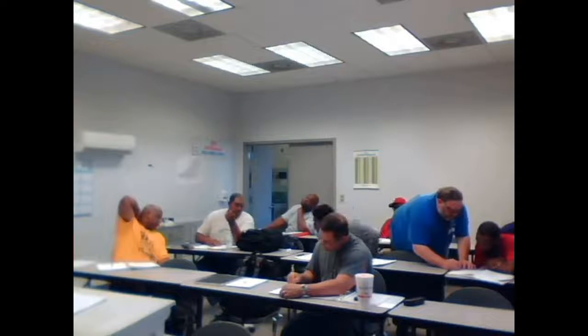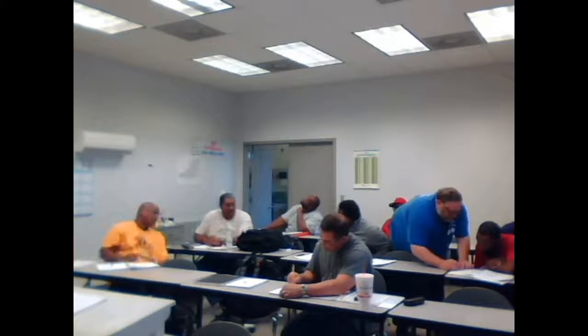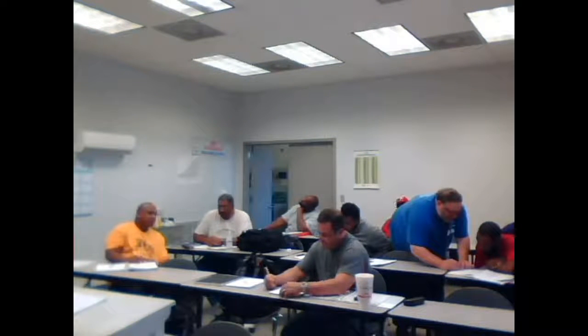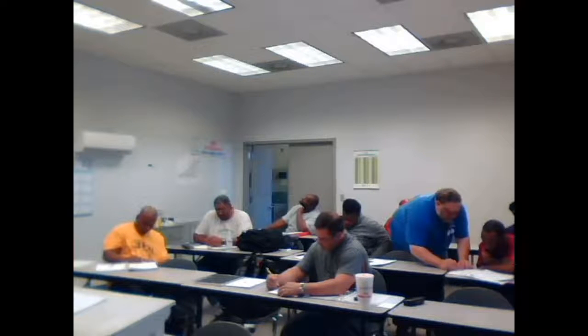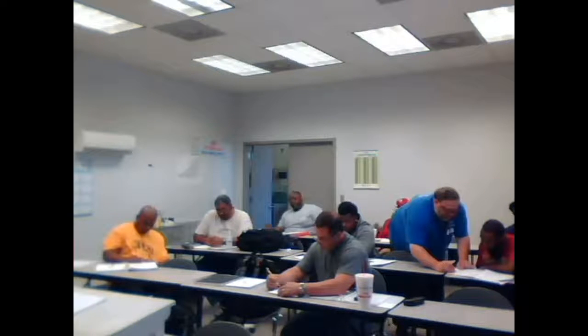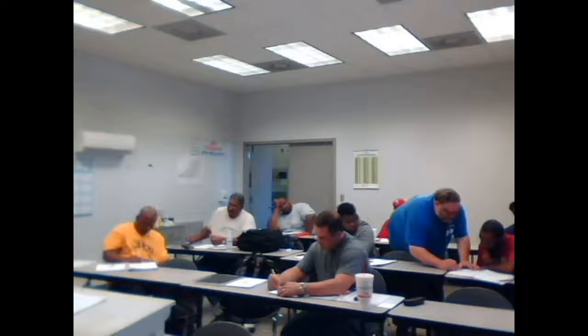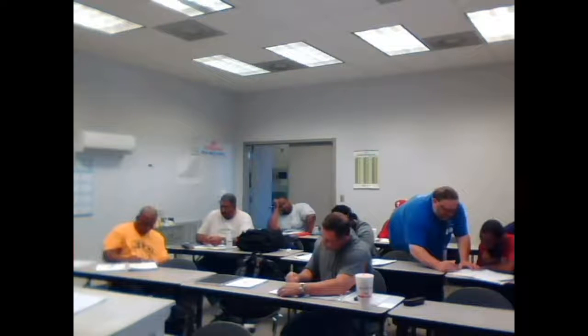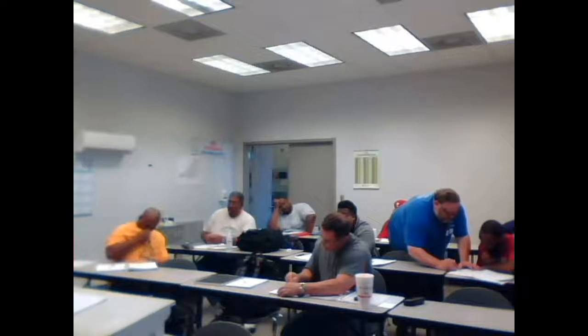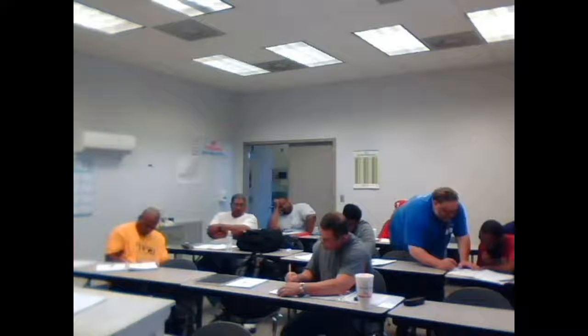Alright, so when you brought L1 to here, this made this T2. This should have gone to there. Since this is L2, this will be T2. Does that make sense? This is 3, 2, 1. And that one went there. Now this one needs to go not just to there, it needs to go to the blower motor. Bring this in here. See what I'm saying? Instead of there. And also to the transformer there. So instead of there, bring that over there. That's right.